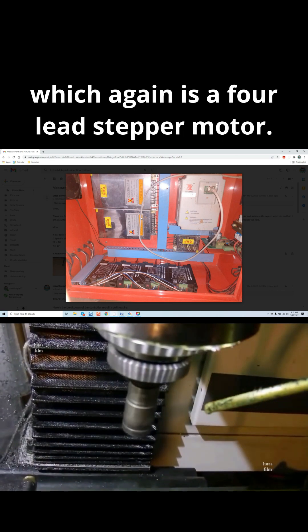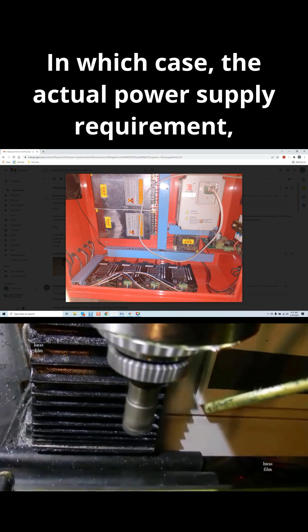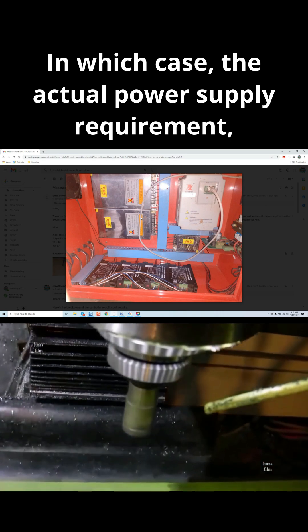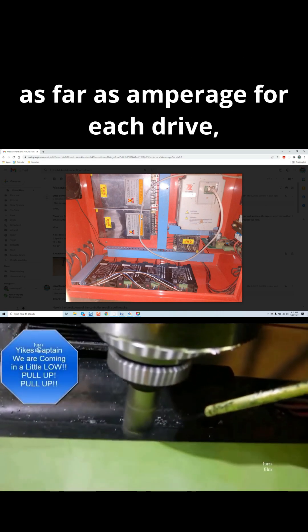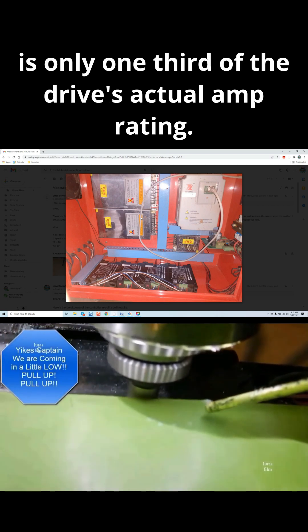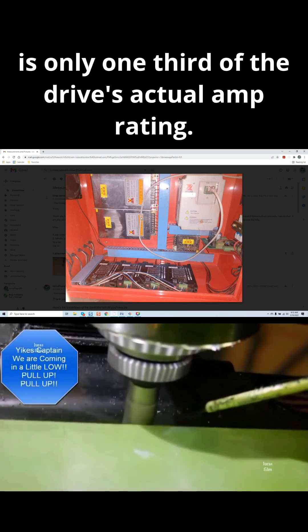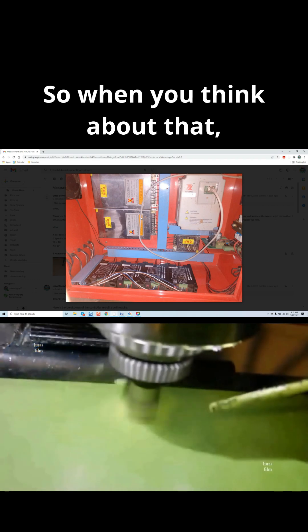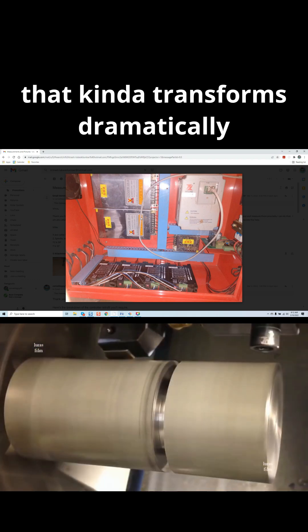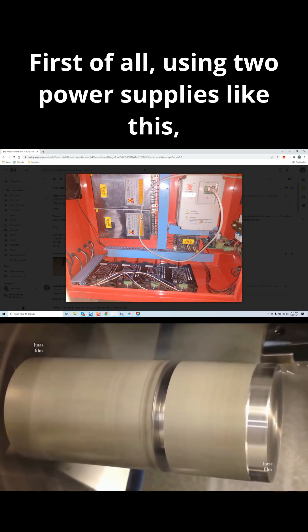In which case, the actual power supply requirement as far as amperage for each drive is only one-third of the drive's actual amp rating. So when you think about that, that kind of transforms dramatically how you build your system.